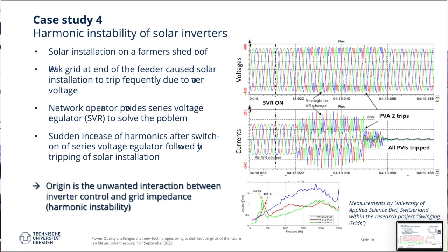Why does this happen? Due to the series voltage regulator, the impedance, not at the power frequency but at a higher frequency or at a harmonic frequency, you can see it here in this little figure, at 350 Hertz, has been changed in a way that it adversely interacted with the control of the solar inverter. And it finally caused the harmonic instability and the inverter tripped. Luckily, not all the inverters have such inefficiently designed controls, but you really have to take care of that.